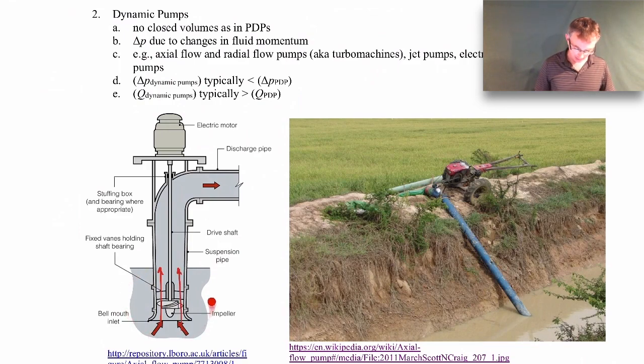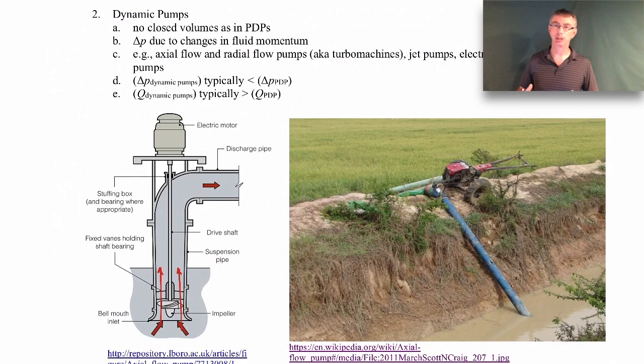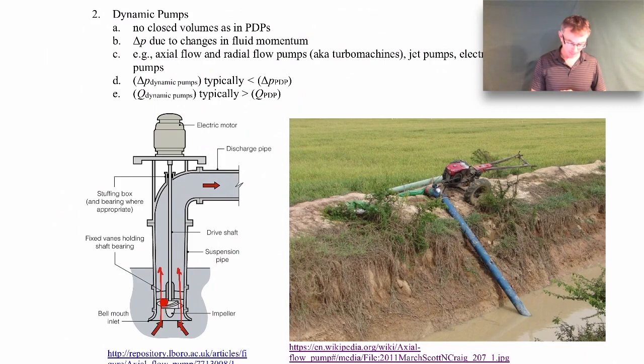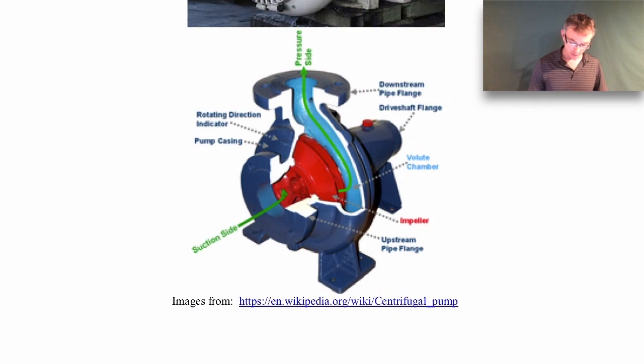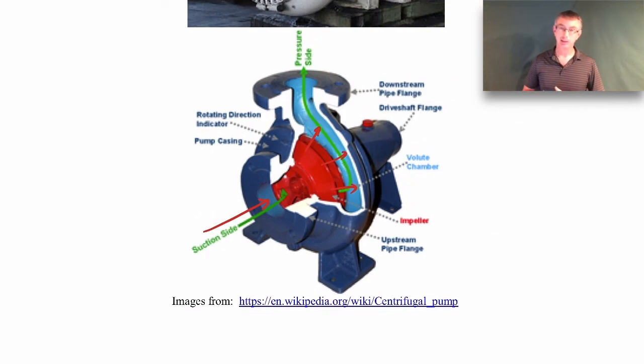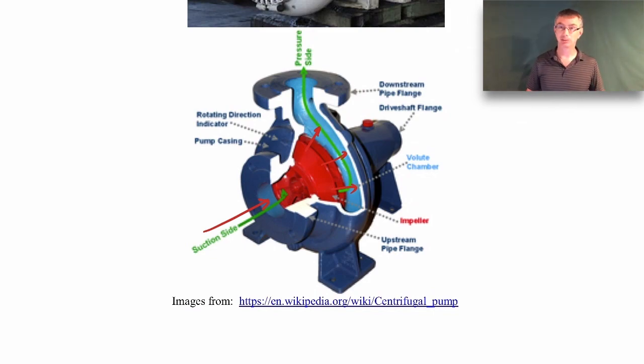The centrifugal pump shown earlier is a radial flow pump — flow comes in axially but goes out radially. An axial flow pump, like the one shown here, has a motor with a drive shaft connected to an impeller with airfoil-shaped blades. It produces a pressure difference across the blades and forces fluid in the same axial direction throughout. There are also mixed flow pumps that combine axial and radial flow — that's called a mixed flow pump.